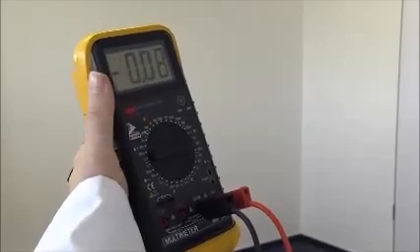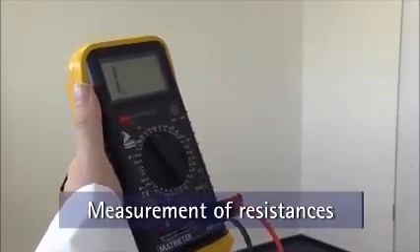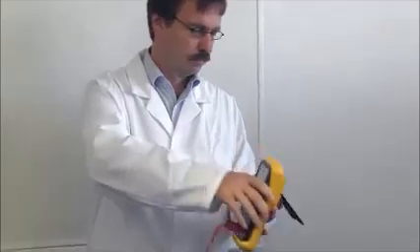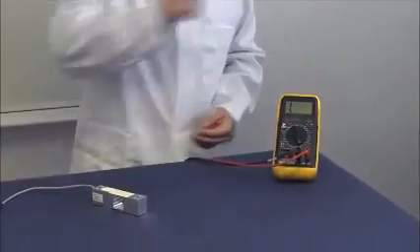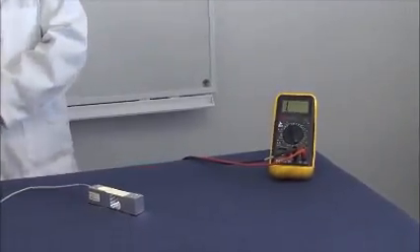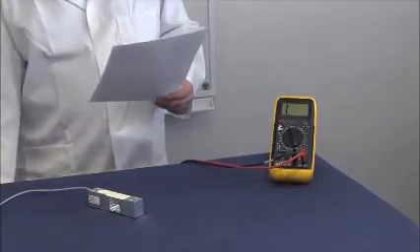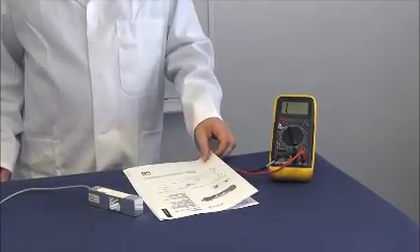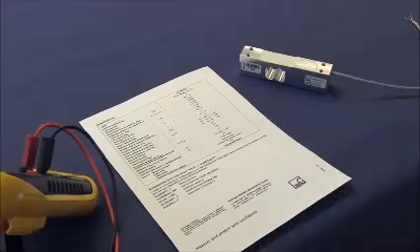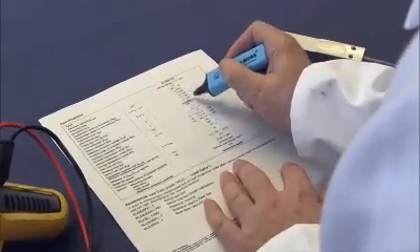The first step for checking the load cell is to measure the resistances of the excitation voltage and of the measurement signal. This step enables you to detect whether all connections in the load cell are correct and the resistance is inside the permissible tolerance range. Be sure to review the datasheet for the corresponding tolerances.